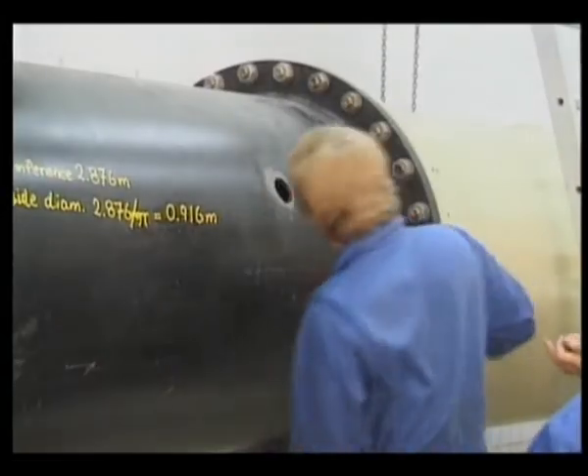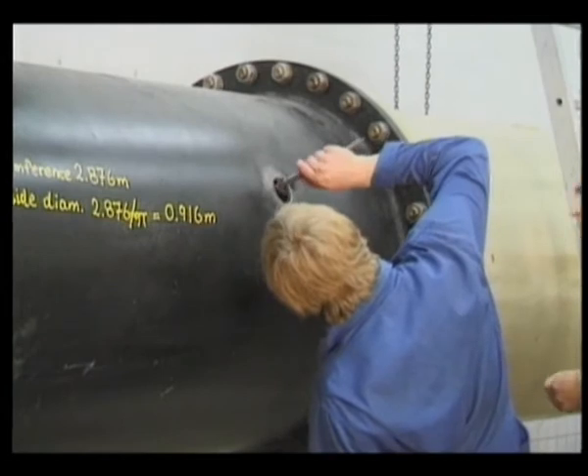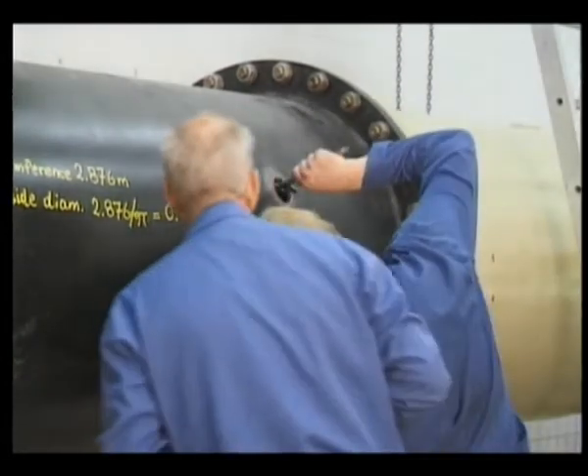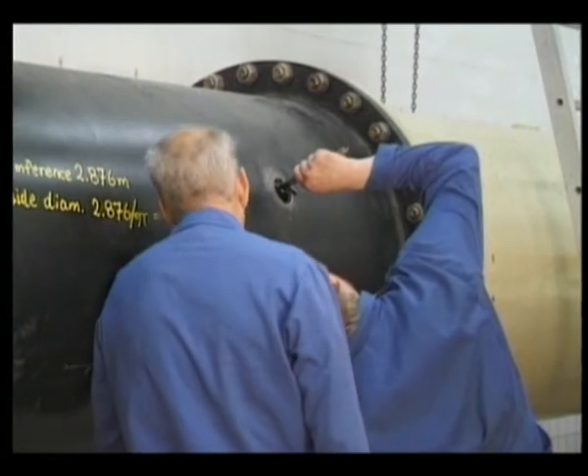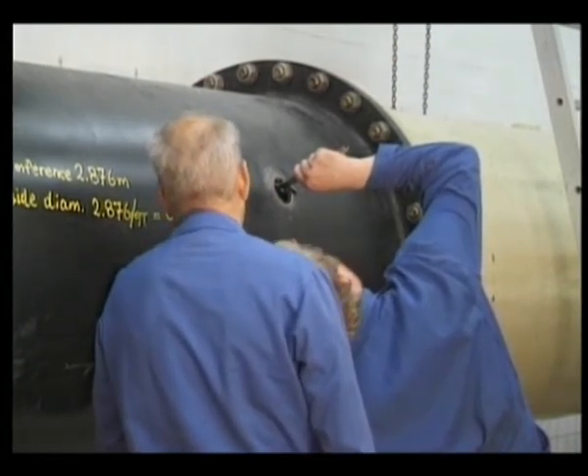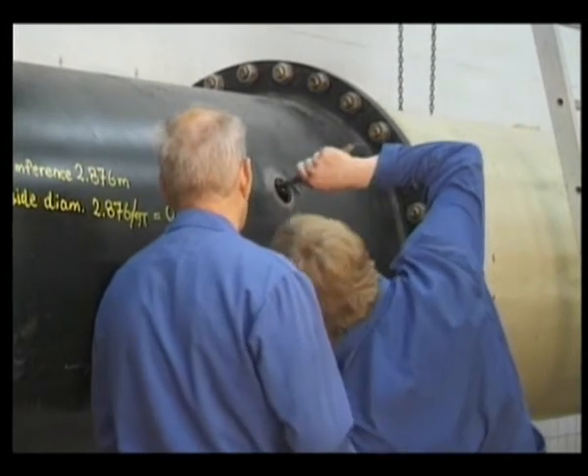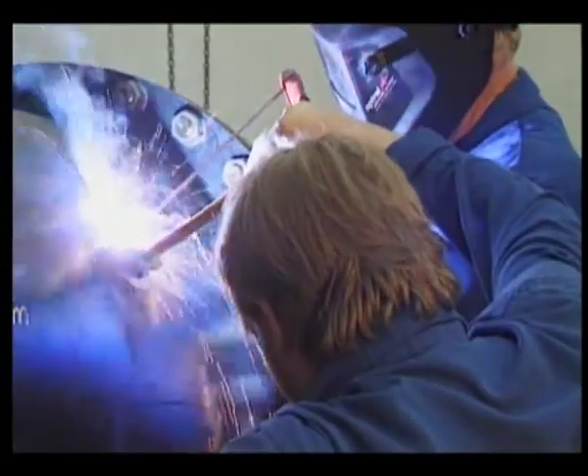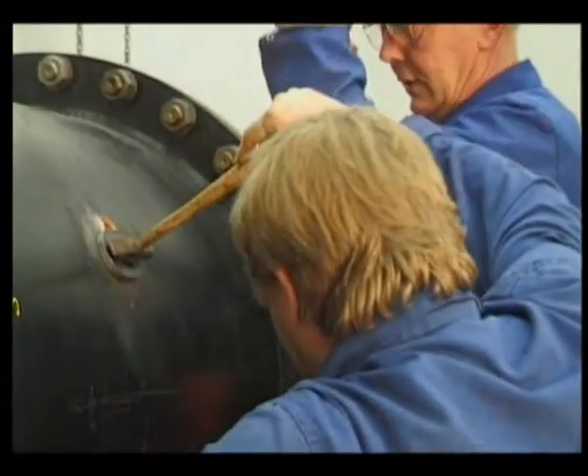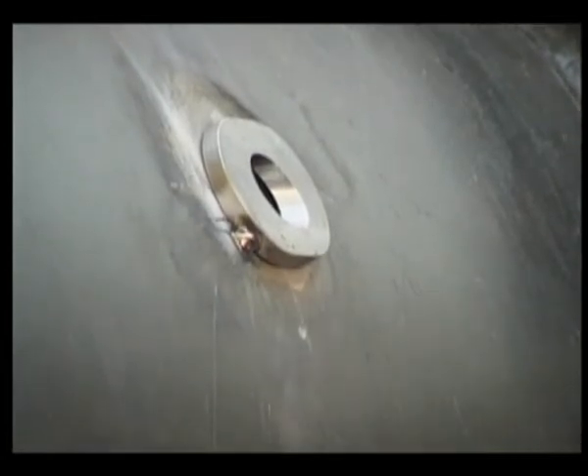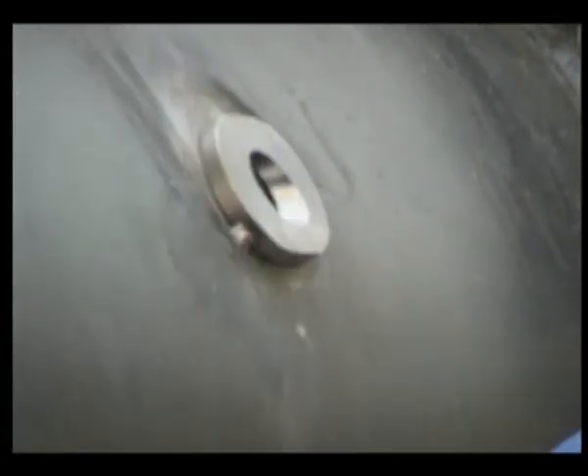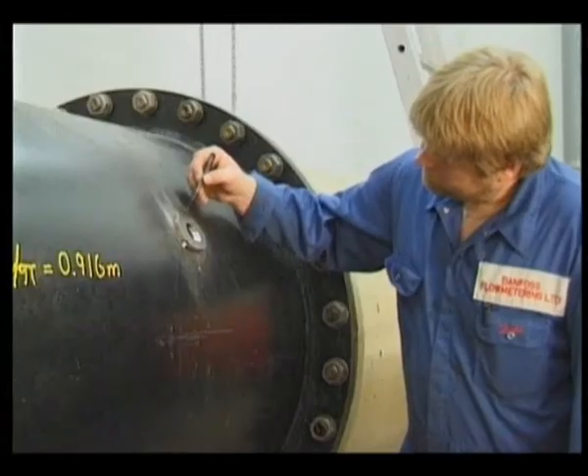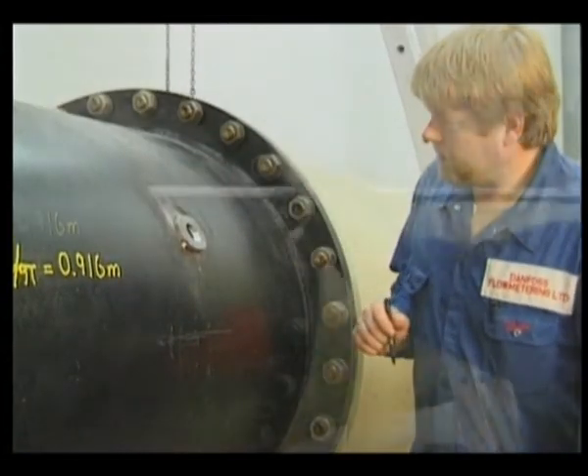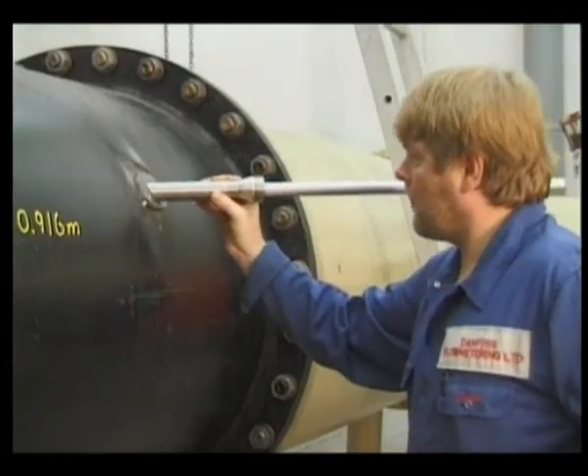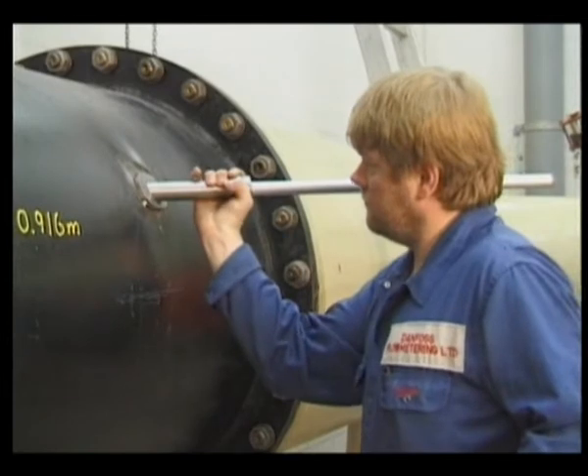The pipe wall thickness is measured to be able to calculate the actual internal diameter. The mounting plates are fastened to the pipe with a pair of tack welds. Before welding the plates all the way around, you must check that the marks on the pipe and the lines on the mounting plates coincide. When the mounting plates have been tack welded on each side of the pipe, check that the transducer holders slide into place easily.